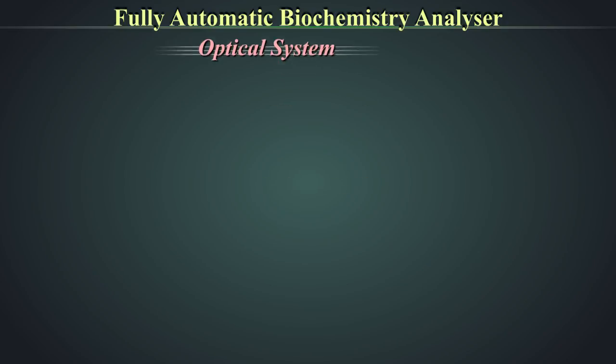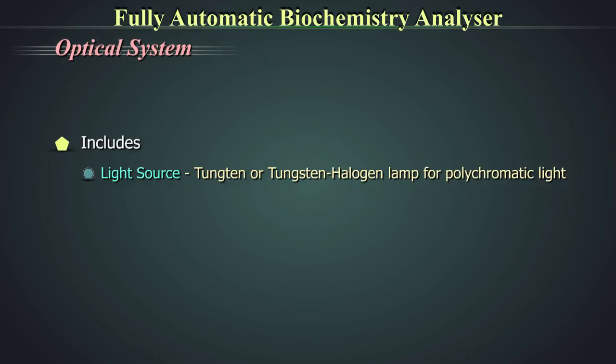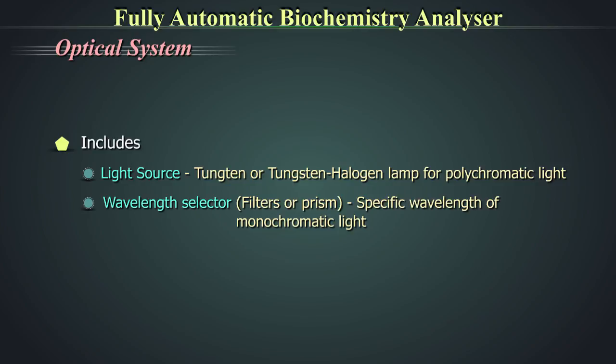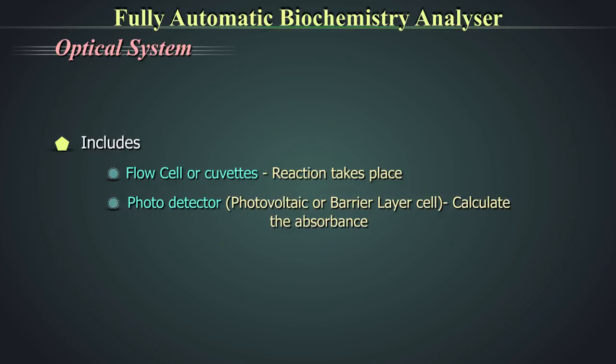The optical system includes the light source, which is a tungsten or tungsten halogen lamp for polychromatic light, a wavelength selector like filters or prism to give a specific wavelength of monochromatic light, a flow cell or cuvette where reactions take place, and a photodetector in the form of a photovoltaic or barrier layer cell which calculates the absorbance.